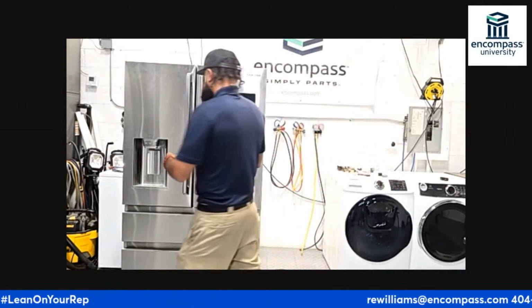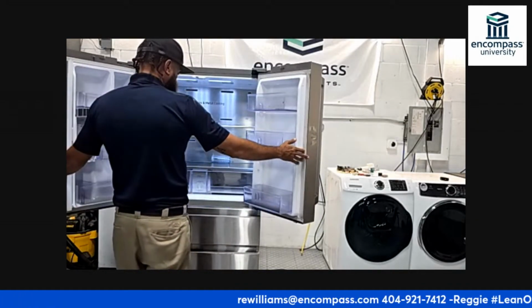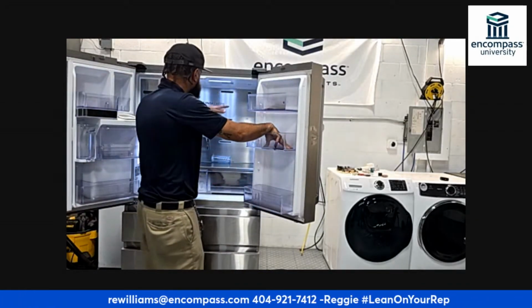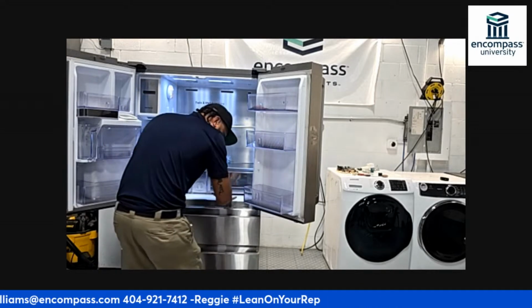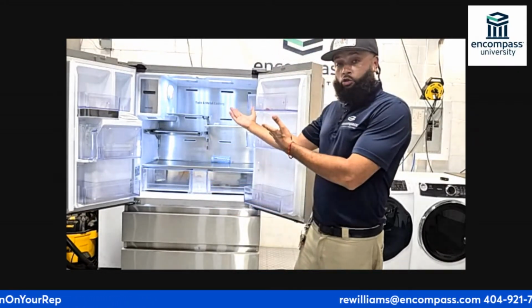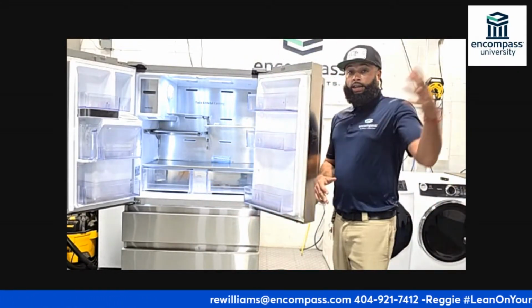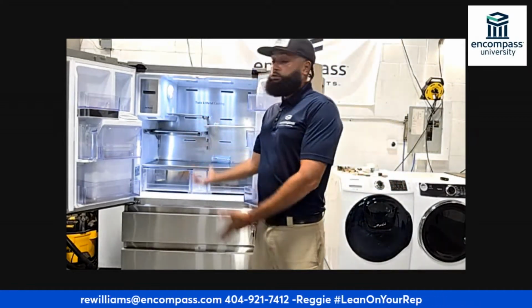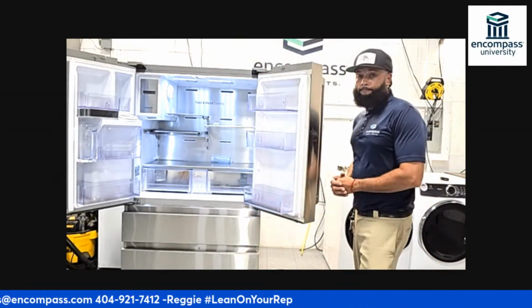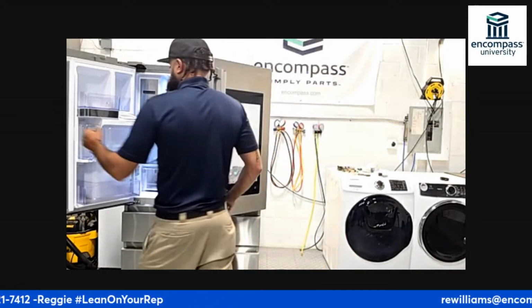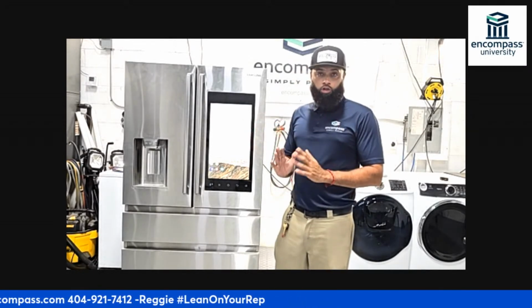But there's a science to getting your temperature. You don't want to get there, open the fridge, and start feeling around checking things out. That's the wrong way to check temperatures, because what you just did was let all your cool air leave the box. Heat travels toward cool, so in theory all your cold air ends up on the floor now. It's important, if you're going to check temperatures in the box, to get in and get out. Open your doors, get your readings fast, then close the doors.